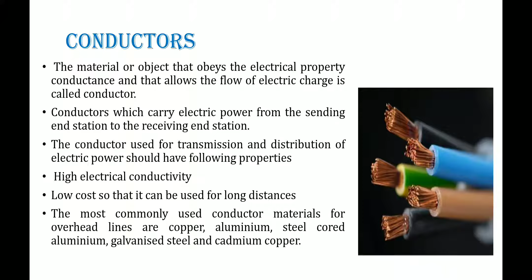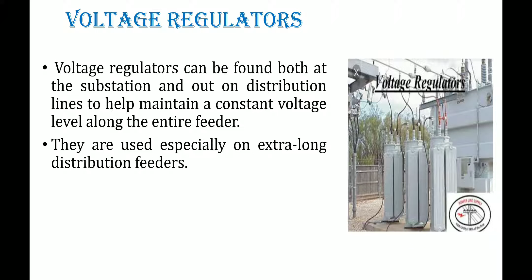Next, an important piece of equipment is the voltage regulator. As the name indicates, it regulates and maintains constant voltage. Voltage regulators are used at substations as well as on distribution lines to maintain a constant voltage level along the entire feeder, especially on extra-long distribution feeders. The main purpose of voltage regulators is to maintain constant voltage levels along the feeders.